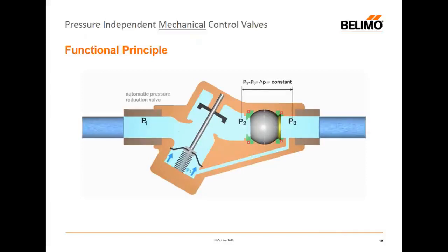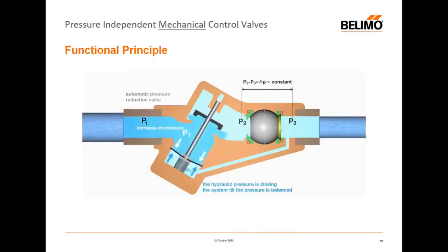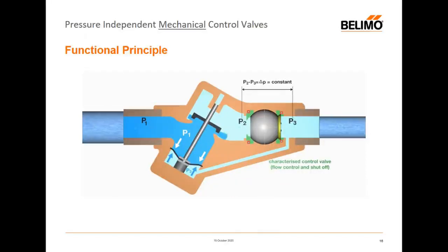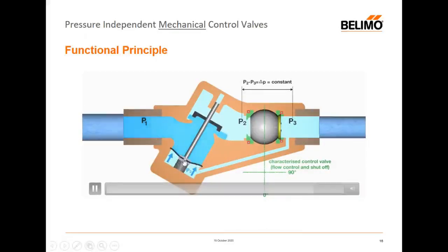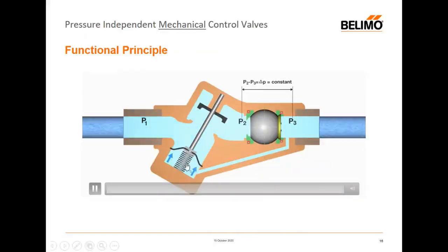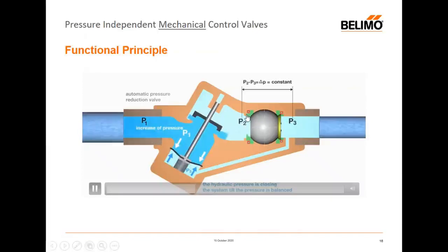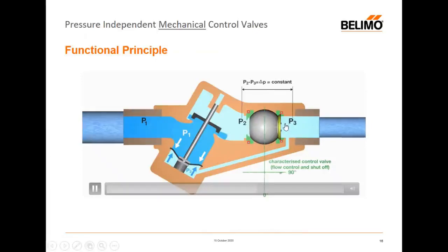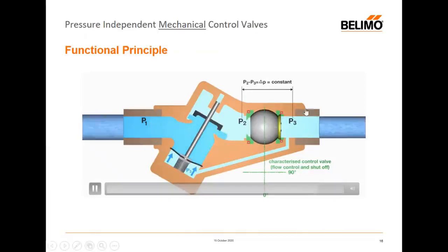So now I want to talk a little bit about pressure independent control valves. So we have this little animation. P1 is the entrance to the valve. We see the flow coming onto the circuit, leaving the circuit, whether it's in the return, and it's pushing down on a spring and a diaphragm. And the spring and the diaphragm is resisted by the spring pushing upwards and along with the combined pressure of P3, which is the exiting pressure. And so there's a balance between these two, which is maintained constant across the seat of the valve between P2 and P3, such that if I know the constant differential pressure, and we talked about KV earlier and the calculation, we can know the flow.